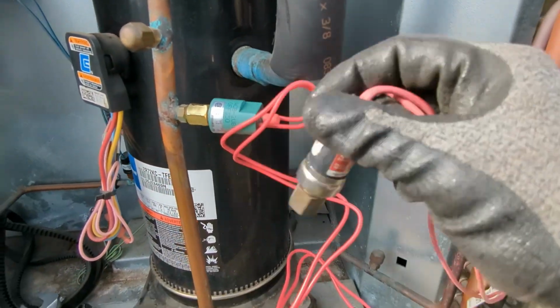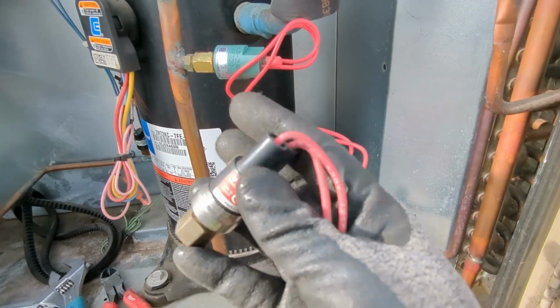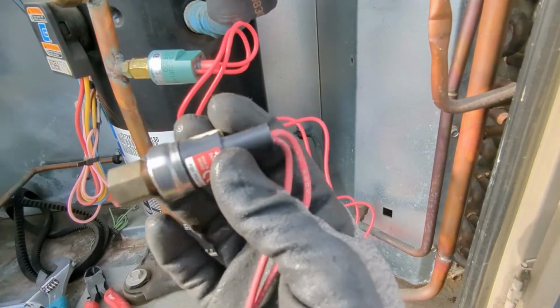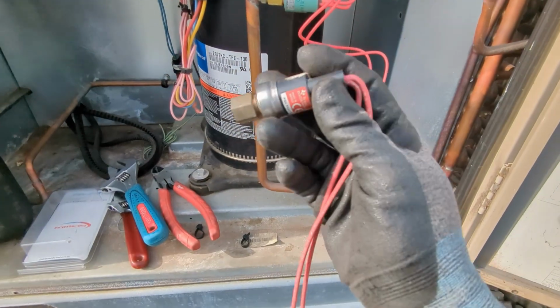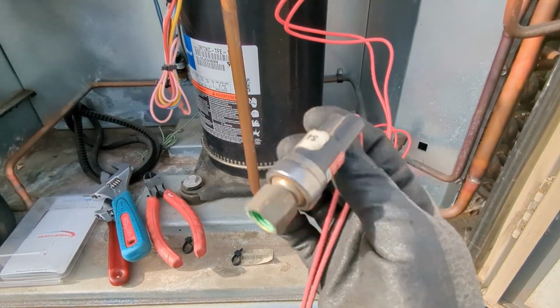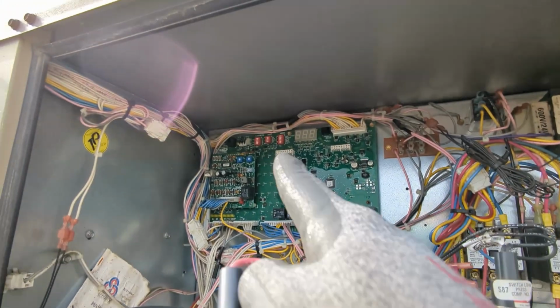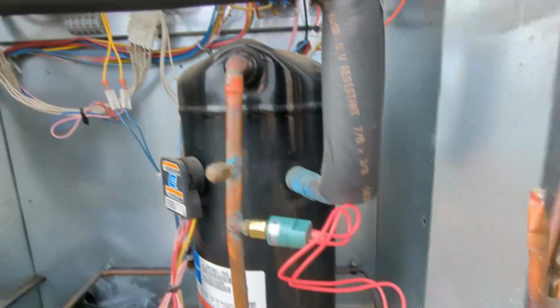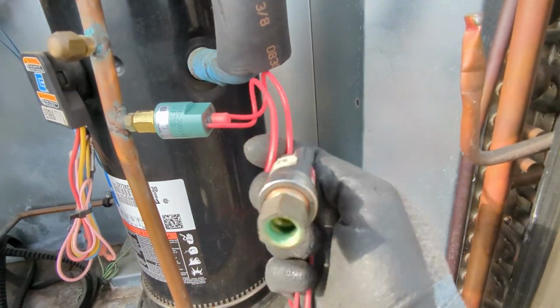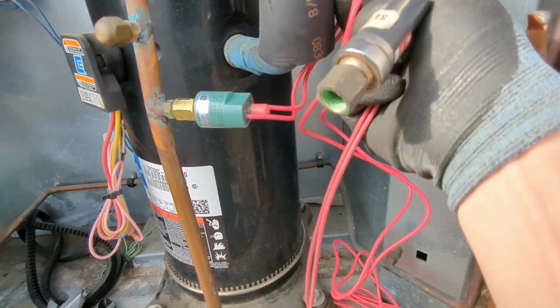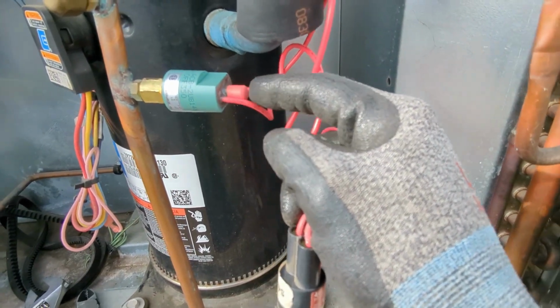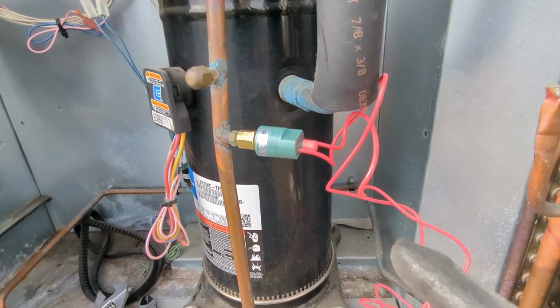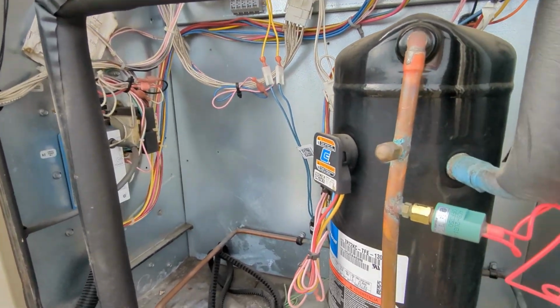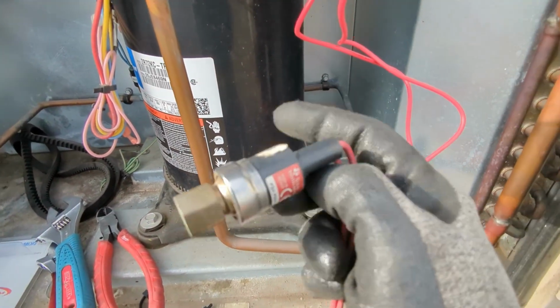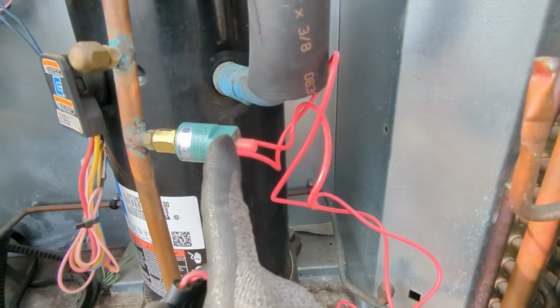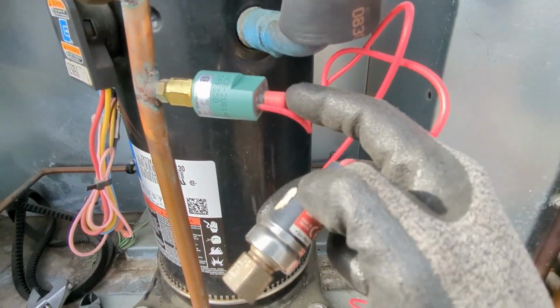So the pressure switch has been replaced. This is the old one. We've decided to replace it with a resettable one. This one automatically resets - it'll do a high pressure event three times and automatically reset, then the third time it'll lock out on that error we found when we arrived. This one, however, will pop and needs a technician to come press this button and reset it, so when that happens we have to investigate why there was a high pressure event. So this one goes three times automatically then locks out, and this one locks out immediately but it's resettable.